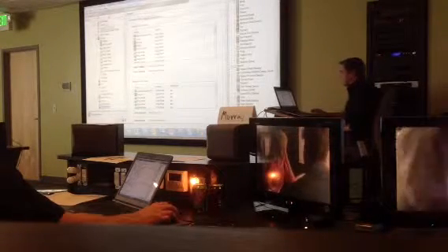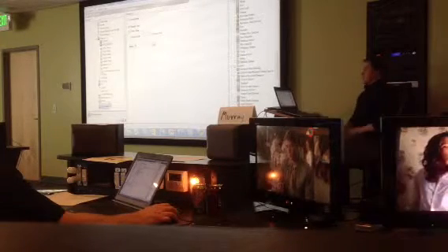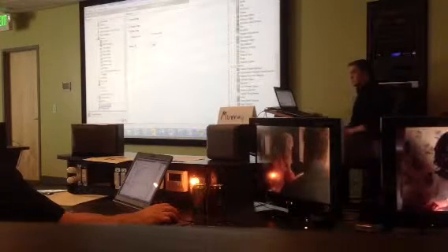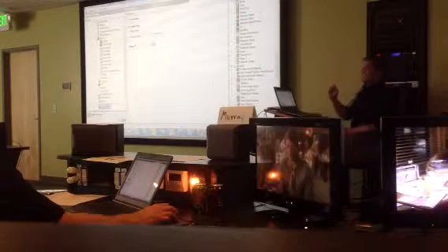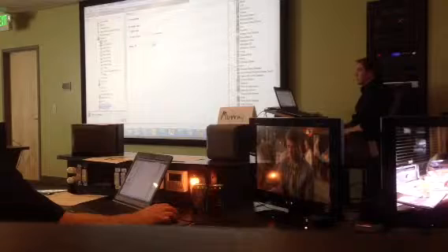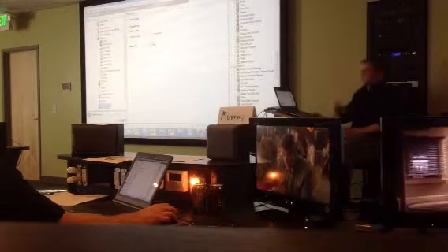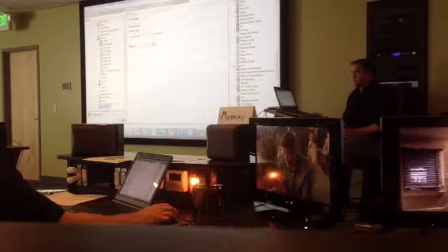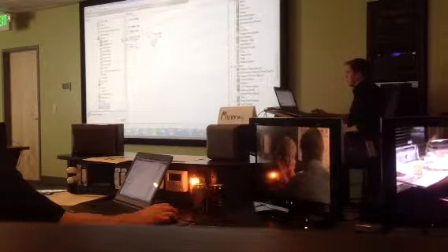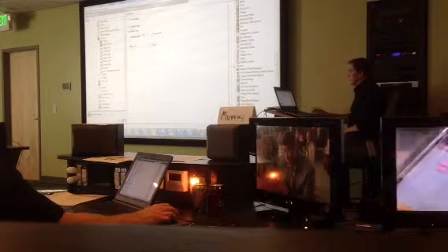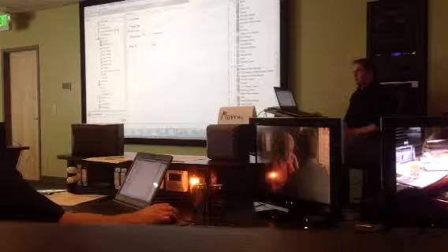Now with a relay, I want to examine its properties. You've got a toggle type or a pulse type of functionality. Toggle type means when you close the relay, it stays closed. When you open the relay, it stays open. Pulse type is where it closes for a brief second, or you could have it be longer than just a second. So whatever you want to set it up to right here. Then it goes back to its original state.